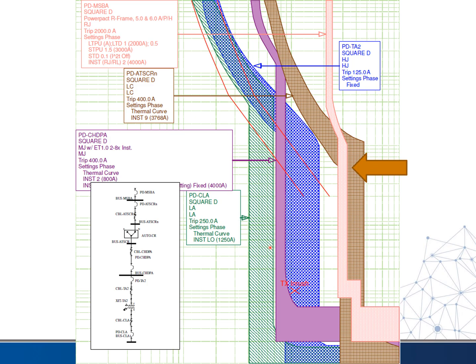The first problem: the main breaker, which is the pink one, should be the furthest to the right, but in this case it is not — this brown one associated with the transfer switch is outside it, so there's a possibility the main breaker would trip before this one. We have a second problem with the purple breaker: if you look at the order, it comes before the blue and the green, so it should actually be outside of those. We have an overlap problem with both our main breaker and the CHDPA breaker, and we need to move them to the right if possible.